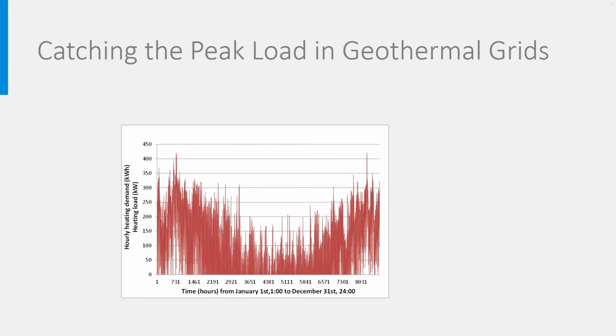If we imagine that the heating profile of the whole neighborhood that must be served by the geothermal plant resembles the one of our building, it would not be wise to size the geothermal plant like this. An enormous surplus of heat would be produced, see the purple surface, that would have to be destroyed. It is much better to size it like that. In the summer, the produced geothermal heat could then be stored in an aquifer thermal storage, for instance, to be used in winter.